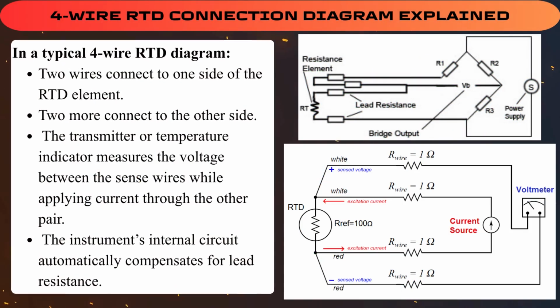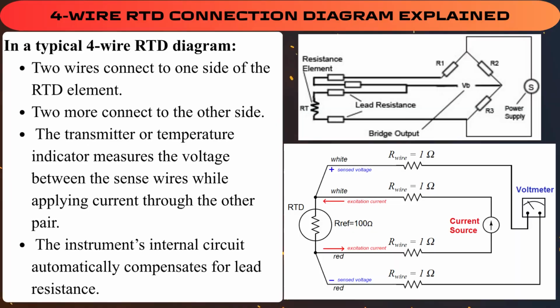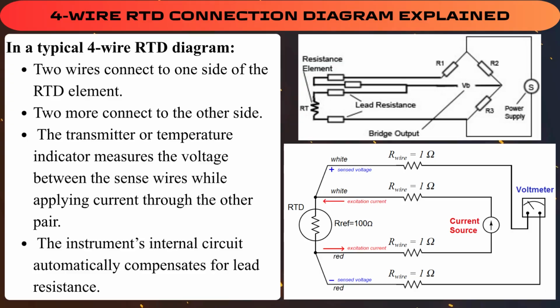4-wire RTD connection diagram explained. In a typical 4-wire RTD diagram, 2 wires connect to one side of the RTD element. 2 more connect to the other side. The transmitter or temperature indicator measures the voltage between the sense wires while applying current through the other pair. The instrument's internal circuit automatically compensates for lead resistance.